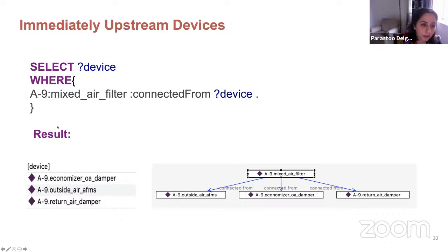When we perform this query, we get the result that the economizer outdoor air damper, the outside airflow station, and the return damper are directly upstream of this mixed filter. This is just a portion of the graph view of the query result, shown as subject, predicate, object.